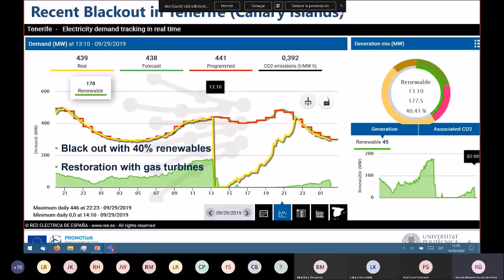This is an example of a blackout last year. It's not the blackout in the UK; this one is less known. It happened in Tenerife, in the Canary Islands, where we have the programmed generation in red and the actual generation in yellow. There was a full zero, and it took about 9 hours to recover. At the time of the blackout we had about 40% renewables, and the restoration was carried out totally using gas turbines. Also, a wind farm that was connected was very quickly disconnected so as not to interfere with the restoration.